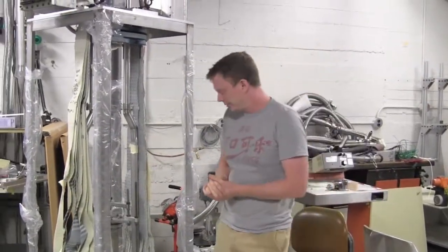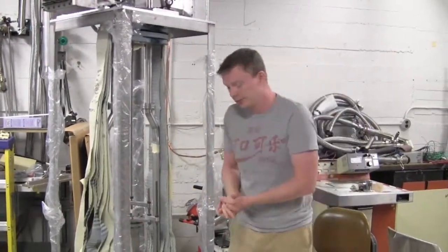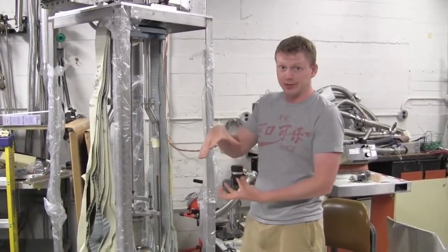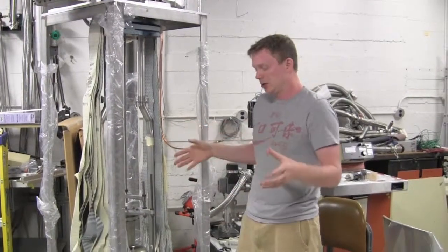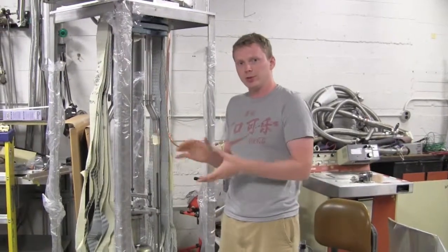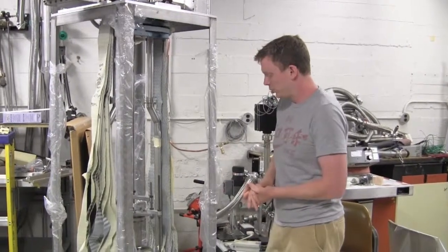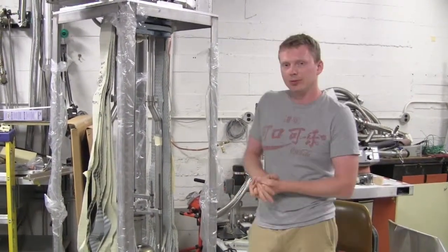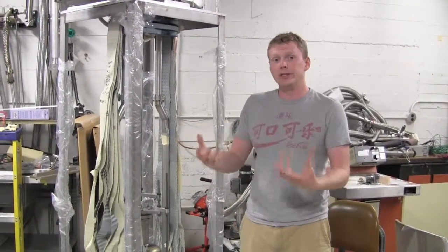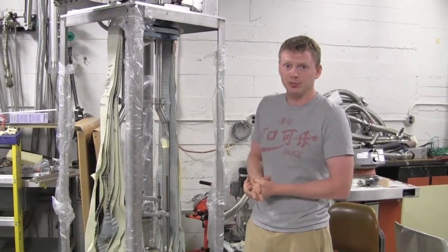Okay, so this is a single cell test cavity. What I'm designing is a baking system that will actually fit within the test stand. The secret of the in situ baking is an ultra-high vacuum being maintained inside, while the outside is actually cooked at 120 degrees Celsius. So the inside will eventually reach 120 C, which is why you hold that temperature for about 48 hours. At which point there's chemistry magic that happens, some physical magic within the actual composition of the cavity, which will raise its quality factor and allow higher accelerating fields before quenching.